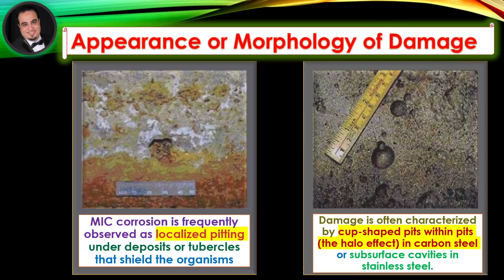Appearance or morphology of damage. MIC corrosion is frequently observed as localized pitting under deposits or tubercles that shield the organisms. Damage is often characterized by cup-shaped pits within pits — the halo effect — in carbon steel, or subsurface cavities in stainless steel.